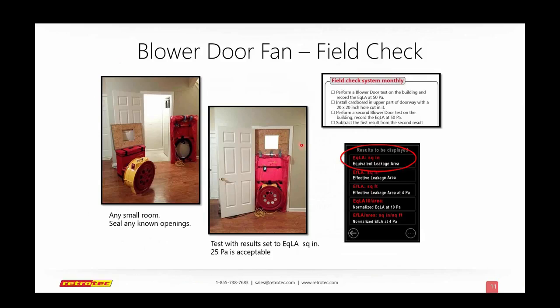But either way, we run the test once to get the leakage with that hole covered up, and that hole, we know exactly how big it is. Then we run the test again, and we deduct the first test, the one without the open hole, from the second test with the known hole. That should be about the size of the hole we cut. So here's the 20 by 20 inch hole, which is about 400 square inches. So the equivalent leakage on the second test should be about 400 square inches larger than the first test. Does that make sense to everybody? Well, great. I'm going to leave this up for a second.